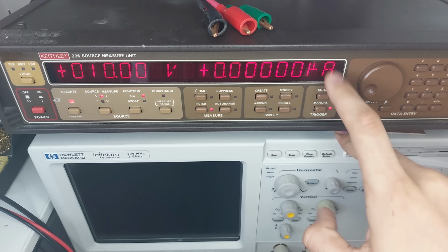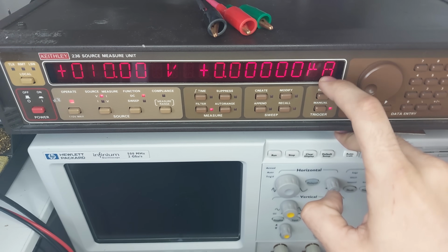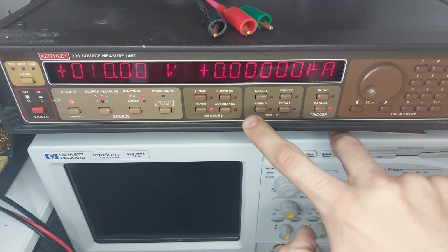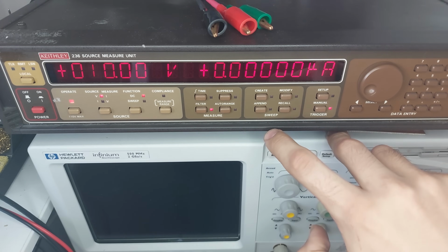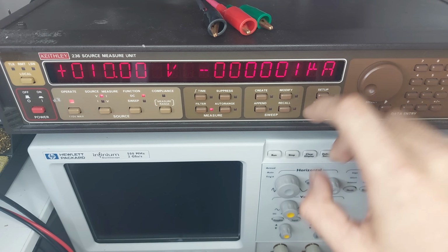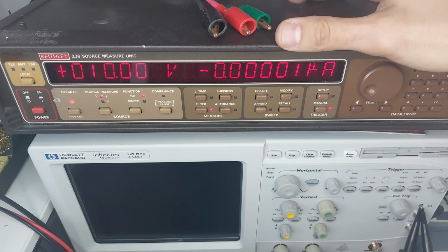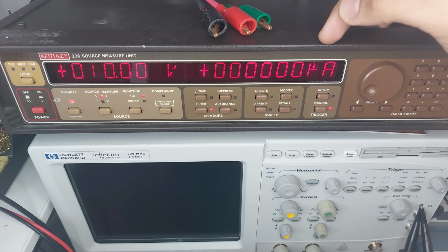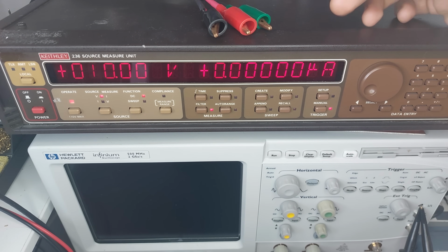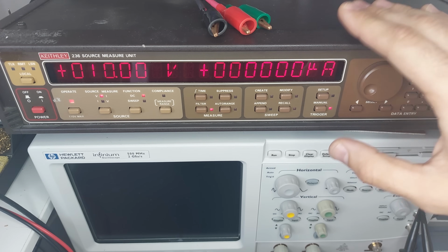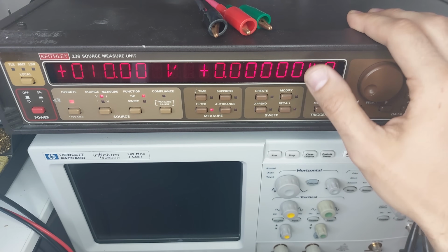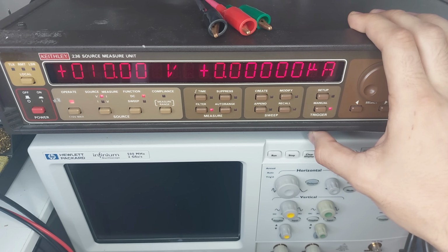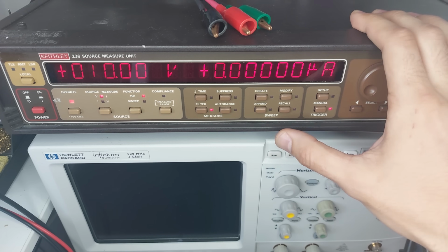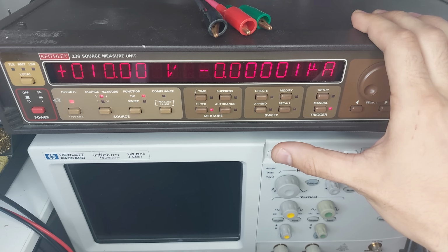it was launched. It was in excess of $10,000. These things were incredibly overly engineered. They were designed to be as good as possible, to get the highest performance that it could get. In the current ranges, this thing is still as good as the brand new 2450 series. Like, it's still got the same resolution, still 10 femtoamps in the measurement resolution, right? Only the brand new electrometers from Keithley do any better than that. And those barely do better than the 30-year-old shoeboxes.